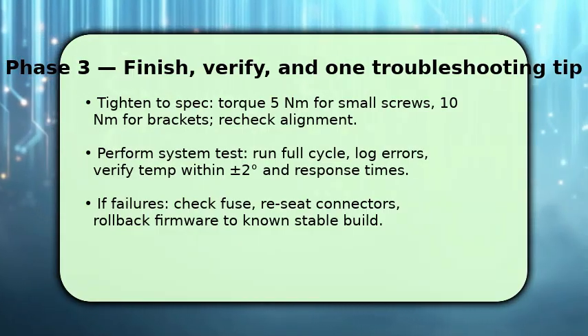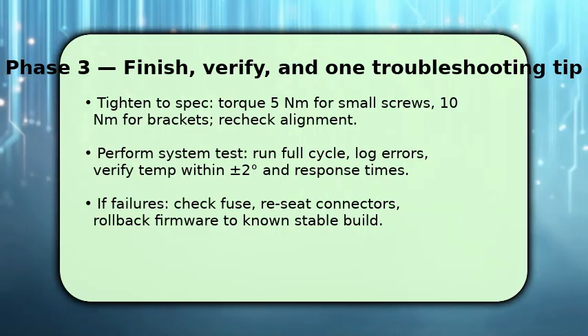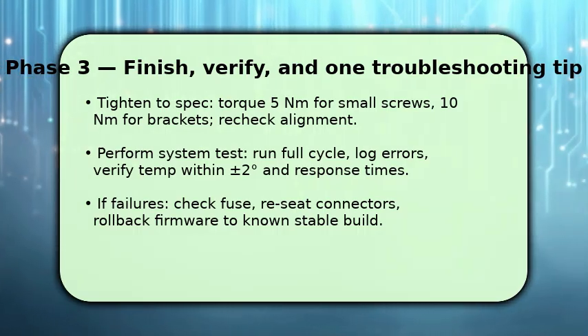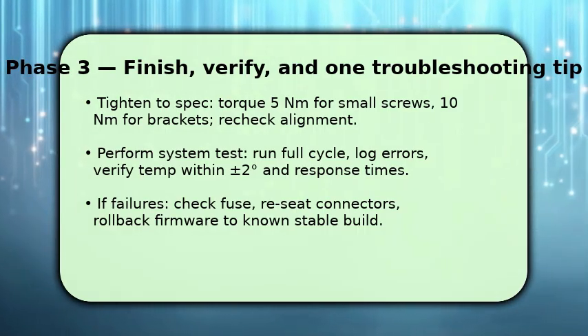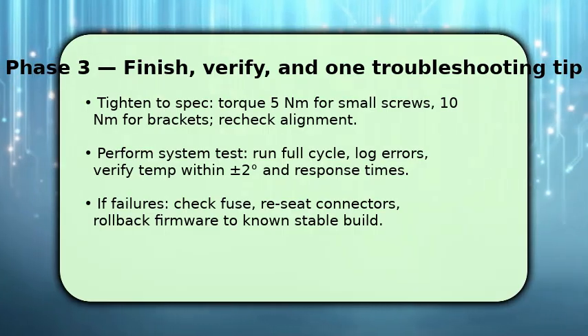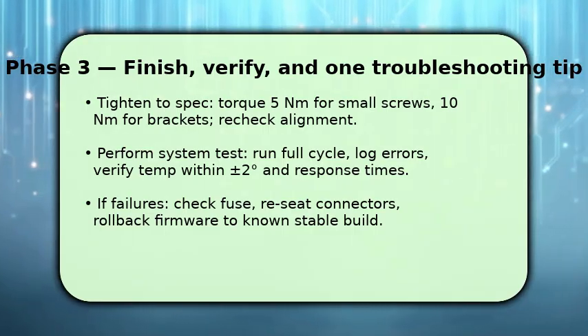One key troubleshooting tip: if behavior is erratic, pull the inline fuse and reseat every connector. Then try a firmware rollback to the last stable build. This resolves most configuration faults.